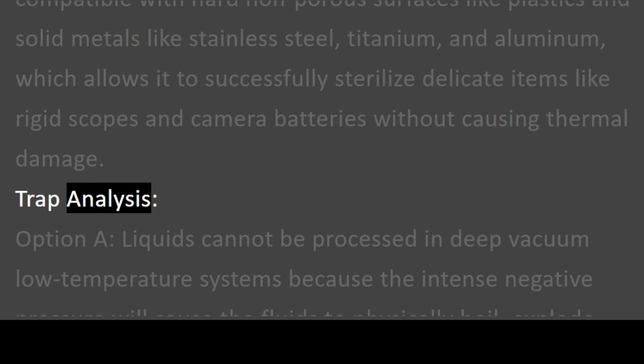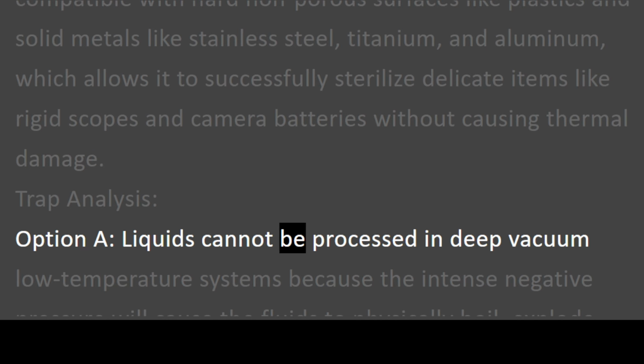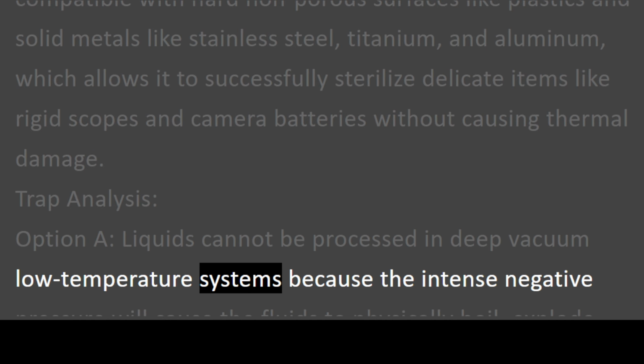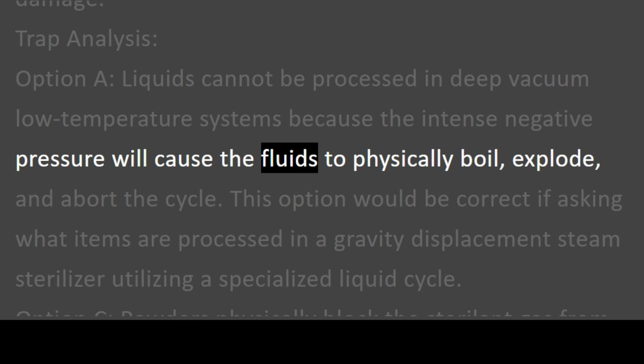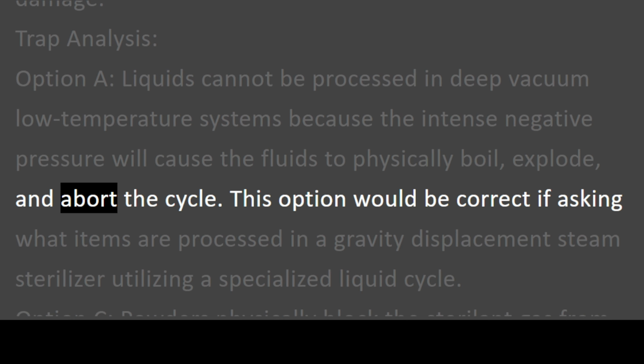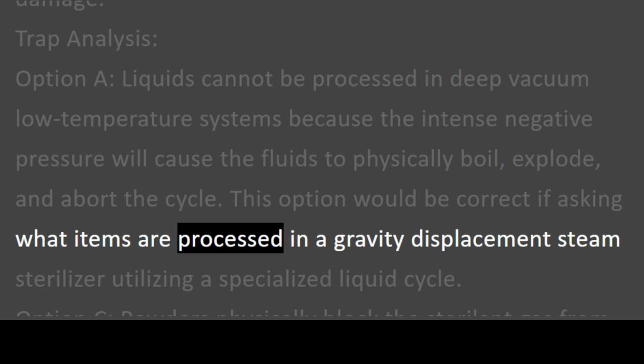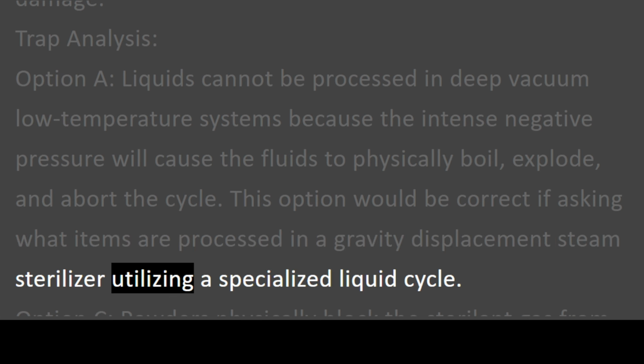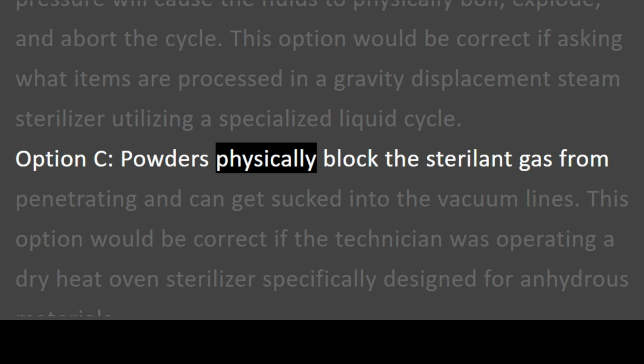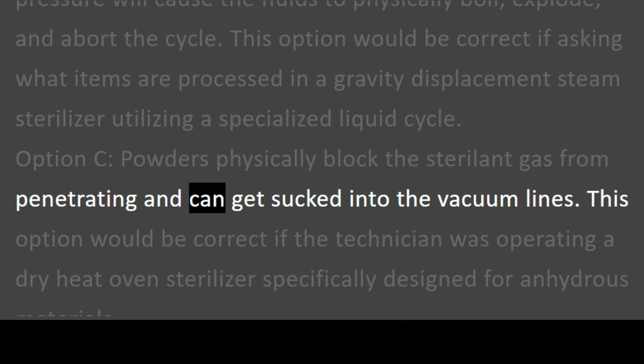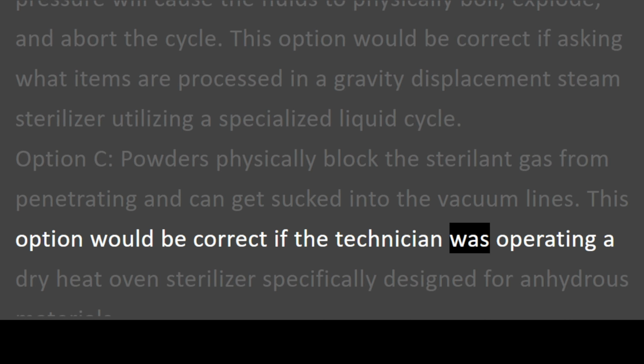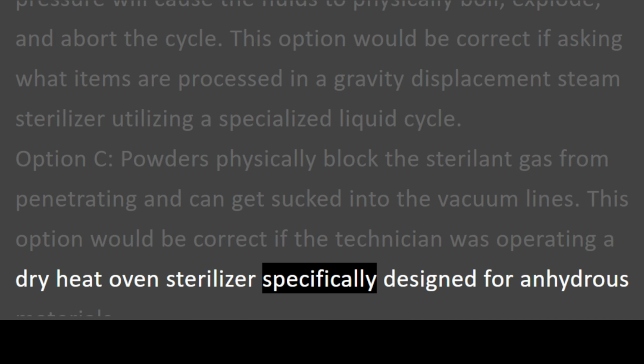Trap analysis. Option A. Liquids cannot be processed in deep vacuum low-temperature systems because the intense negative pressure will cause the fluids to physically boil, explode, and abort the cycle. This option would be correct if asking what items are processed in a gravity displacement steam sterilizer utilizing a specialized liquid cycle. Option C. Powders physically block the sterilant gas from penetrating and can get sucked into the vacuum lines. This option would be correct if the technician was operating a dry heat oven sterilizer specifically designed for anhydrous materials.